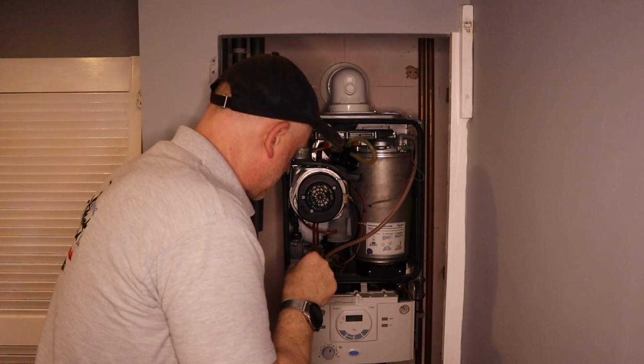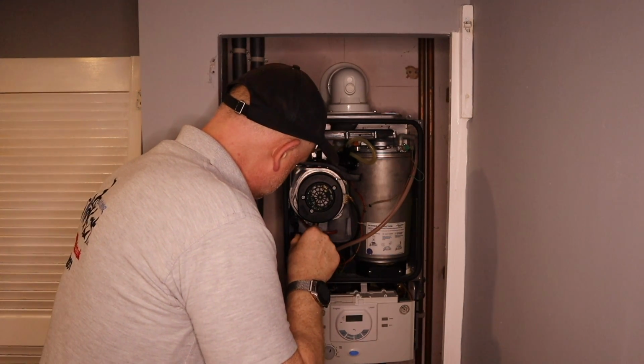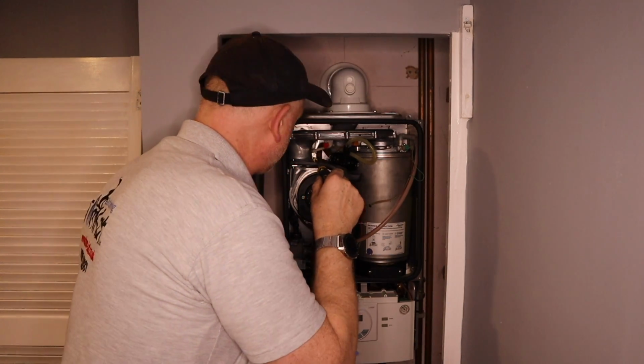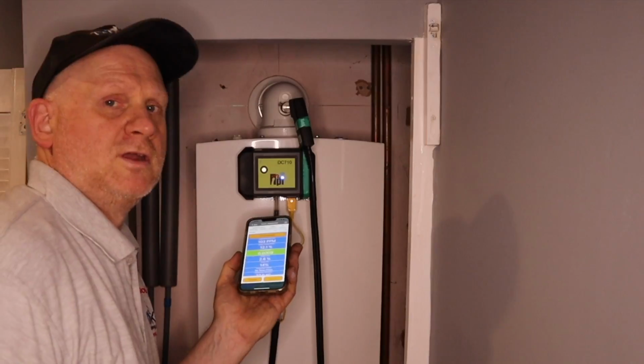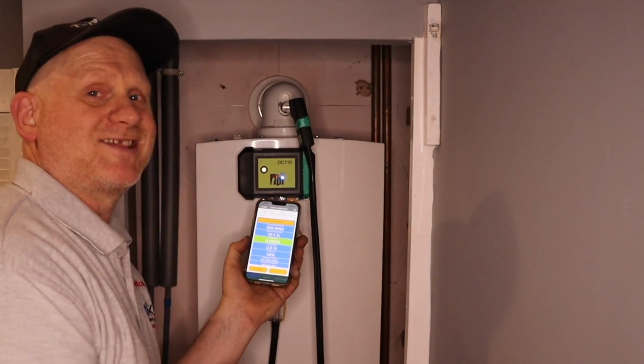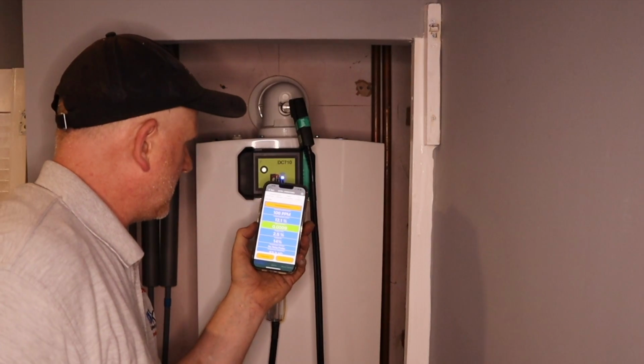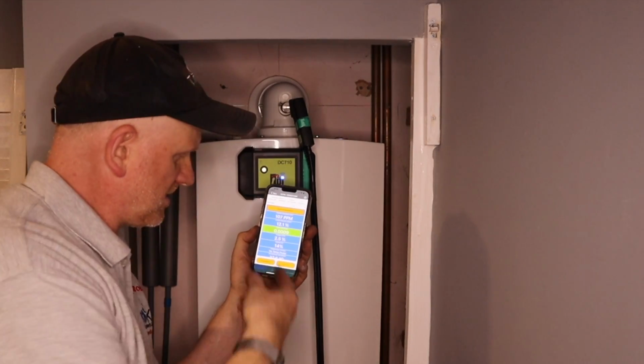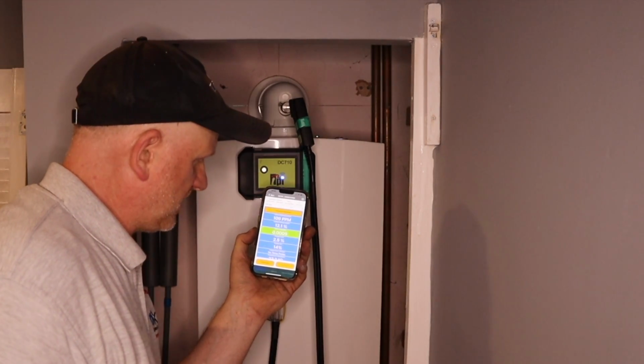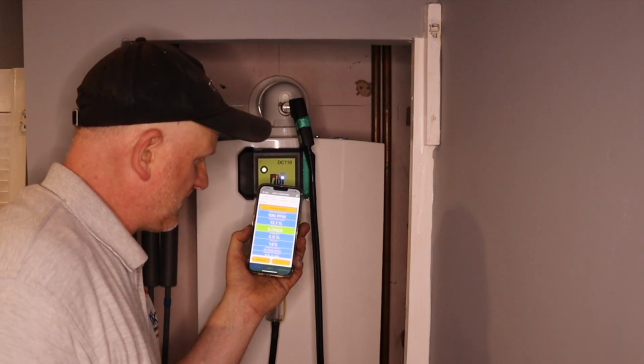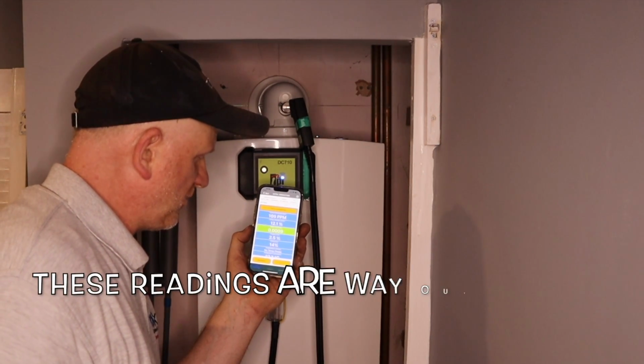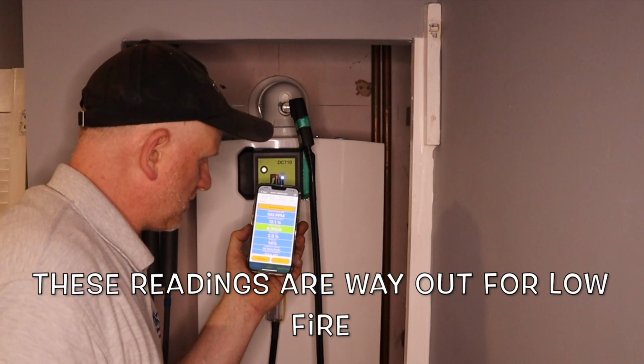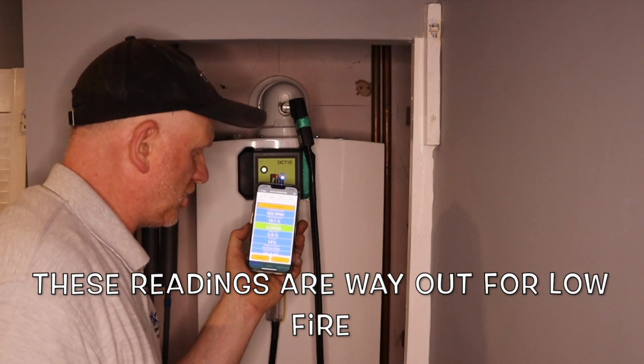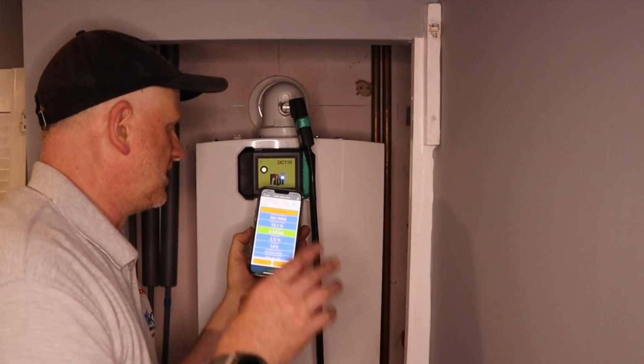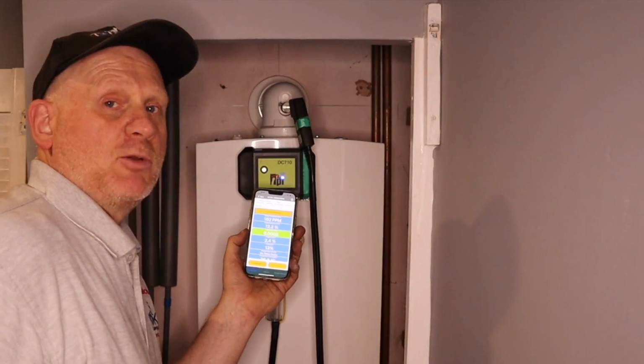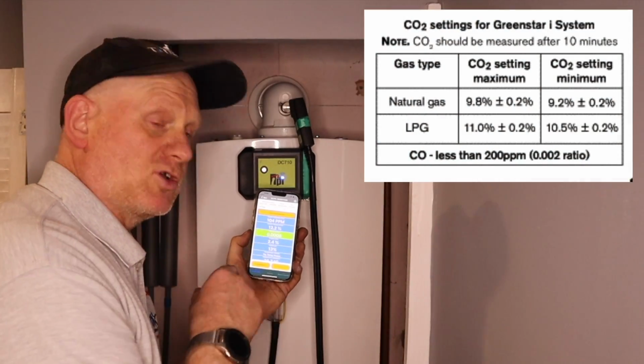So everything looks good inside here. So I can put the cover on now and flue gas analyse it. I'll put the cover back on, just analysing it in low rate. I've got my DC 710 on with the app, and it's reading 106 ppm for CO, 12.1 for the CO2 with a ratio of 0.0008.